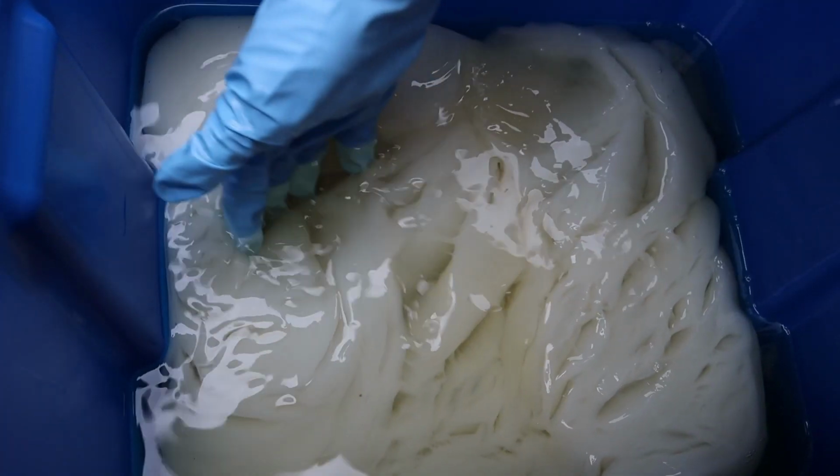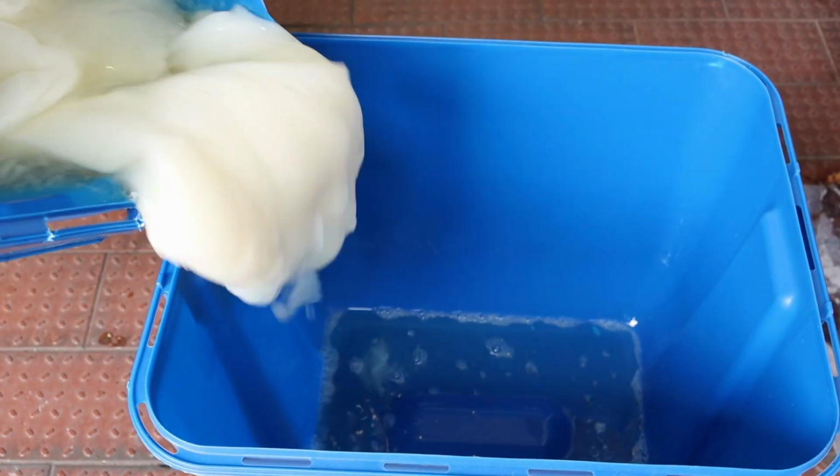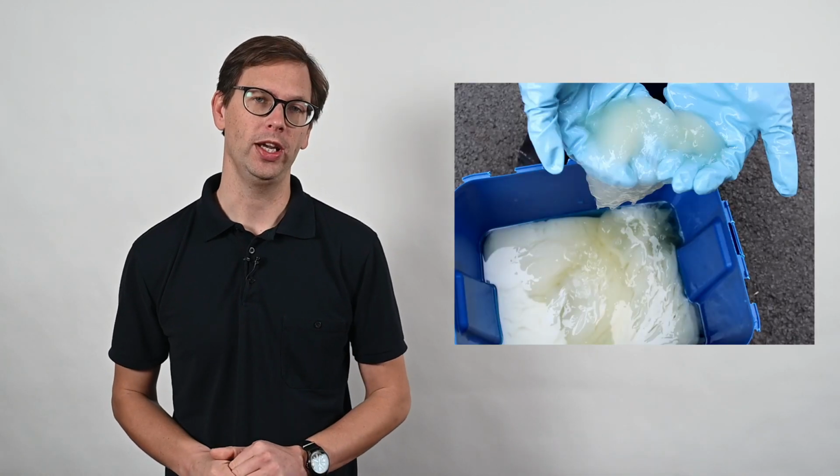This is what we found in the foam tank of a fire engine last year. And it is actually firefighting foam concentrate. Well, it was, because obviously this is only waste. This video is about how that happened, how it can be prevented, and what foam concentrate is affected.